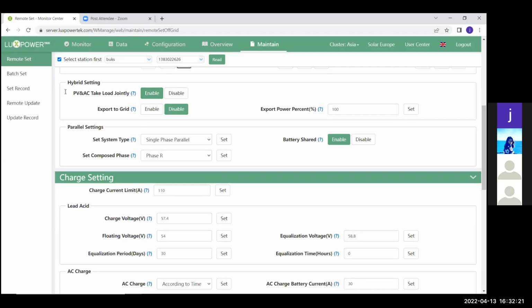Now, this specific setting will always allow your inverter to backfeed a slight amount of power. You can have up to half a kilowatt, so 500 watts, of backfeeding power through the day. So if you have a system that is extremely sensitive to backfeeding at the meters, then you can't use the PV and AC joint function, because it will trip the meter at the box.